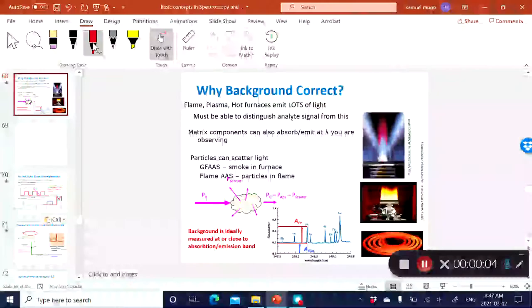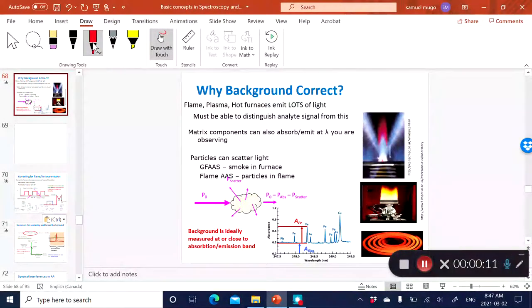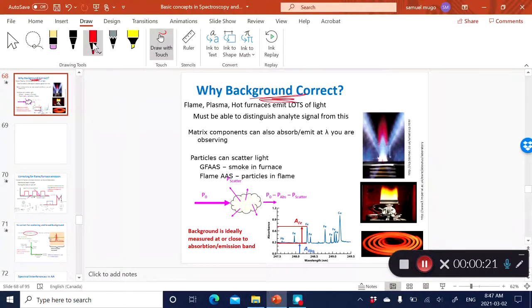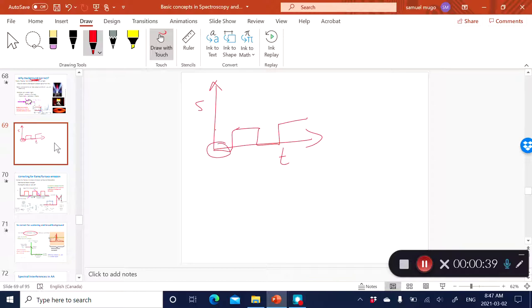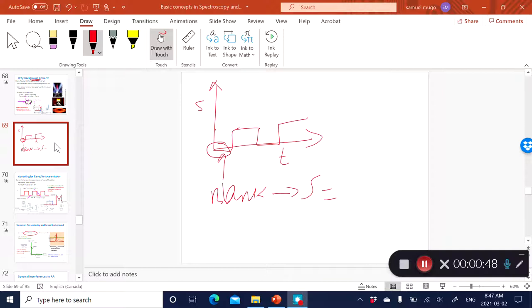In the last lecture we talked about how flames are essential to cause the atomization of the sample in atomic spectroscopy. They also cause a problem referred to as the background. In an ideal setting, your signal as a function of time should look flat, meaning that when there is no analyte or when there is a blank, you essentially have a signal equal to zero.